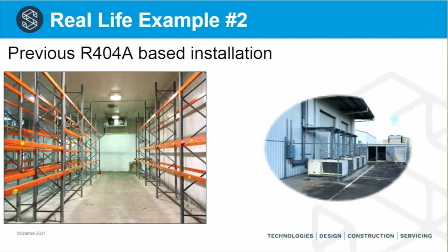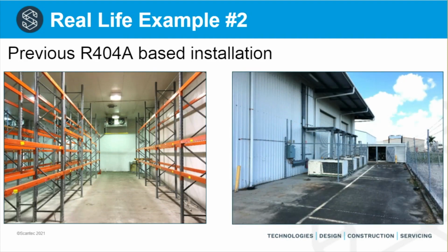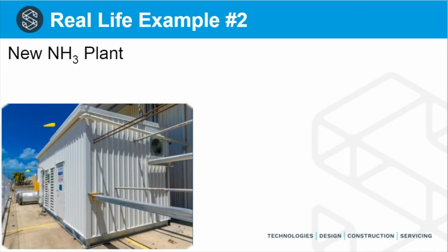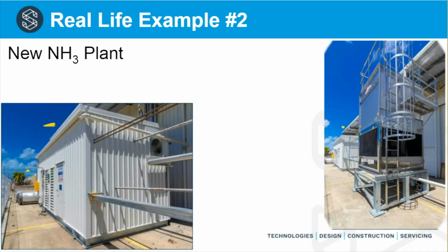This is the replacement of an HFC 404A system. Here you see pictures of the 404A installation as it was. A very small facility, approximately 3,200 cubic meters of refrigerated volume. It's a food service business. The Freon plant had been lying dormant for a couple of years. You can sort of see that in the right-hand picture. It looks decidedly unused. This was replaced with a new dry expansion ammonia plant that was pre-assembled in the workshop.